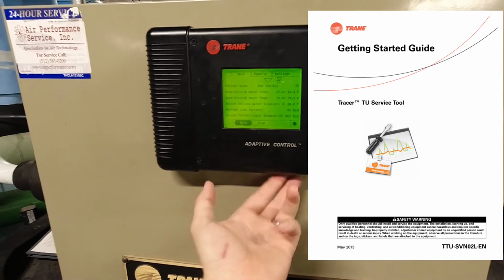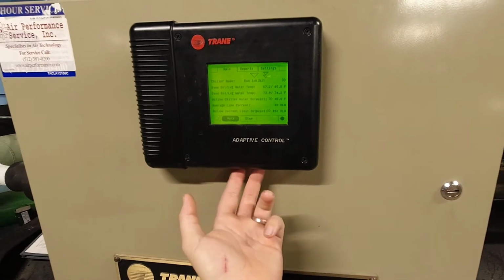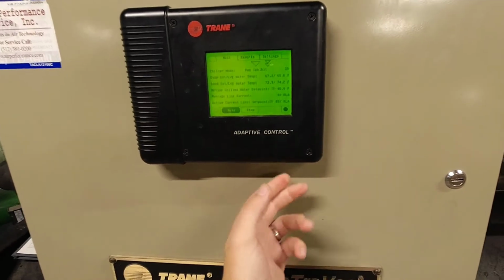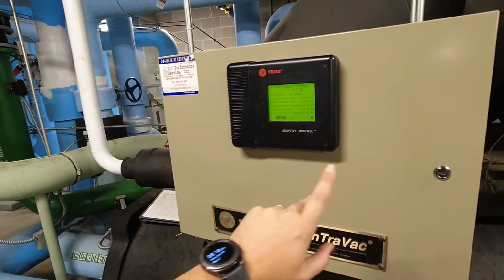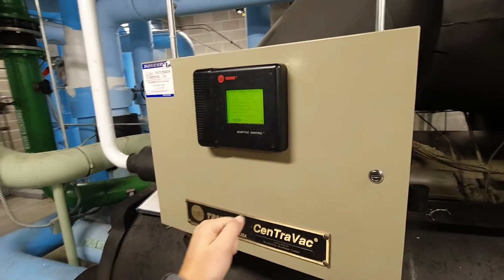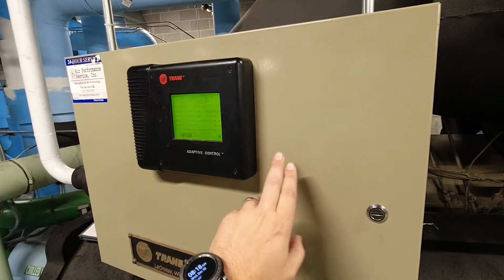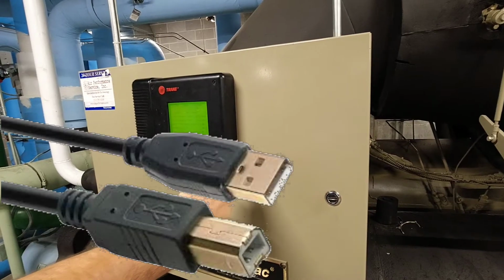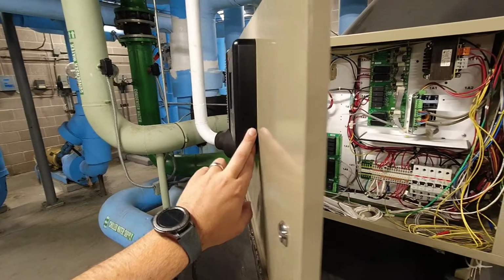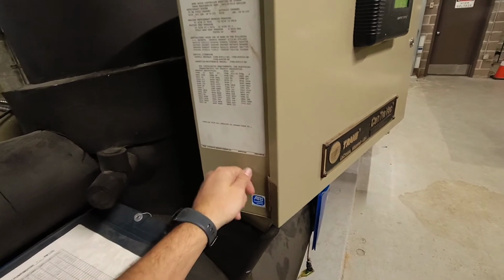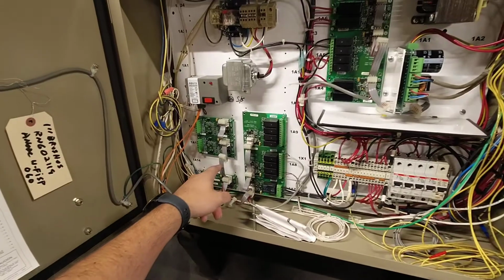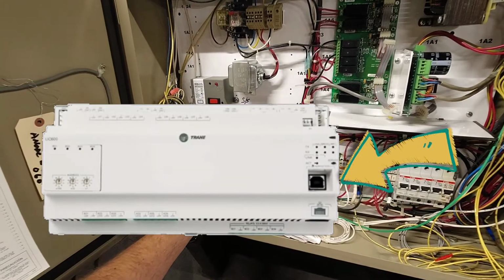So this particular controller has a serial port here at the bottom. It's got a little flapper you can open. That's where you would connect to it. If you had the newer one, it's got a serial port for this, like I think it's a USB-B style cable that you would see on a printer, and you could either plug in through the side of the display. It's got a port here on the side of the panel you can plug in, or when you open the panel, they'll have a TU controller right here, a little automation-looking controller you can plug into.